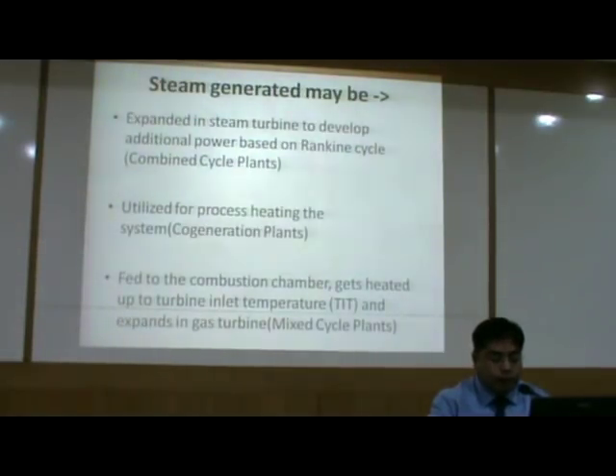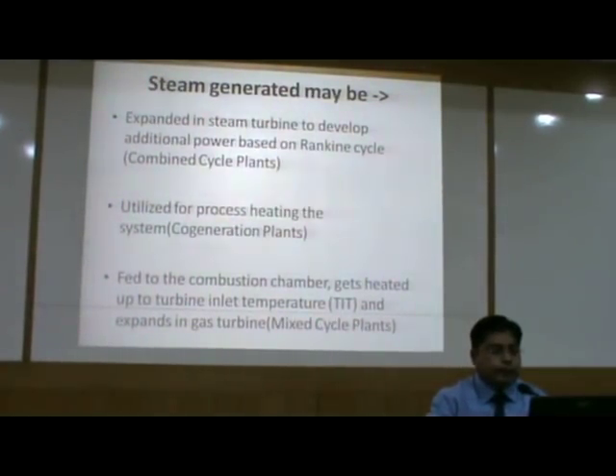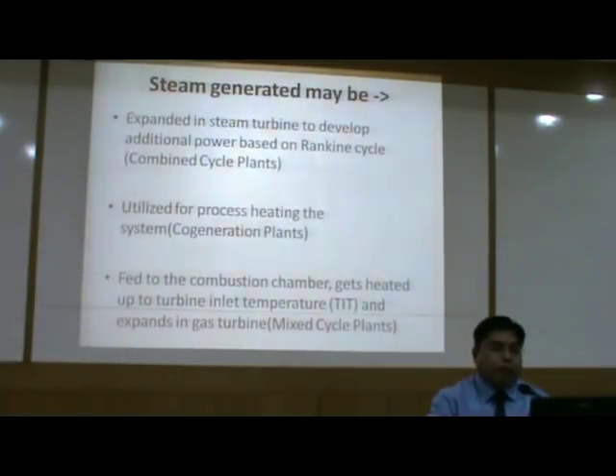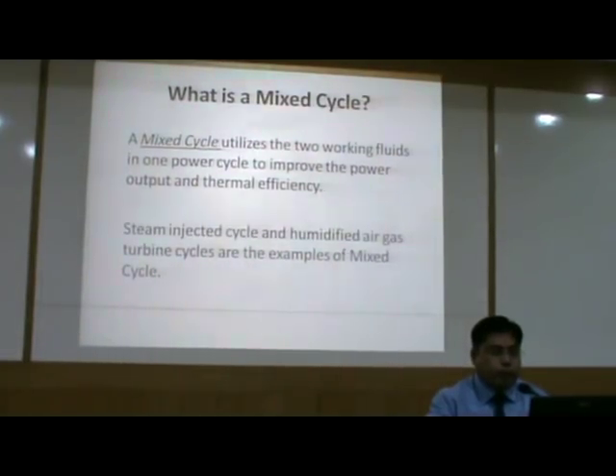The steam generated by use of the recovered heat from the HRSG may be expanded in a steam turbine to develop additional power based on the Rankine cycle. It may also be utilized for process heating, like in co-generation plants, or it may be fed to the combustion chamber, heated up to the turbine inlet temperature, and expanded in the gas turbine — which is known as mixed cycle plants. My emphasis in this lecture is on the use of mixed cycle.